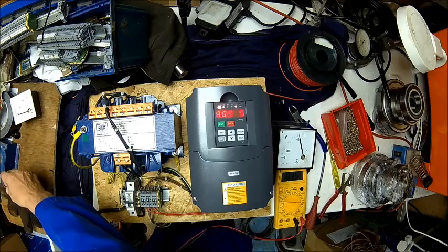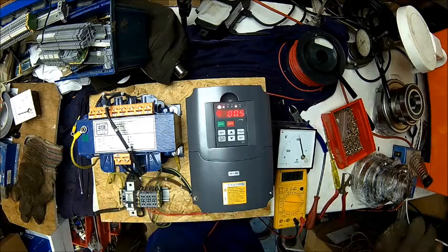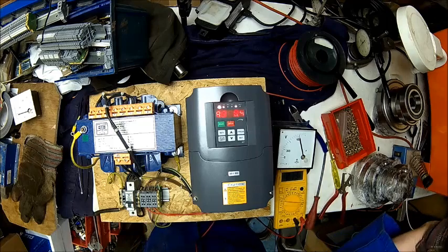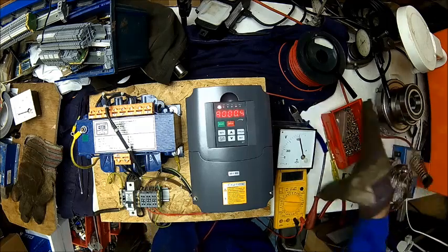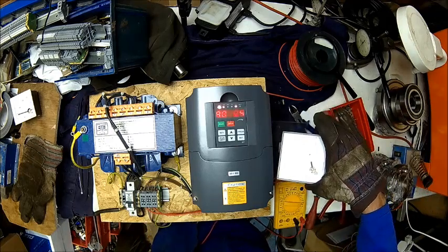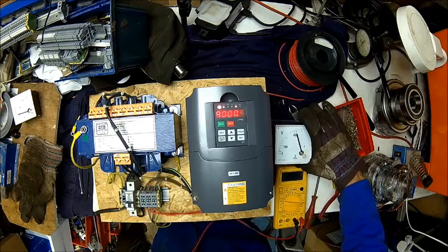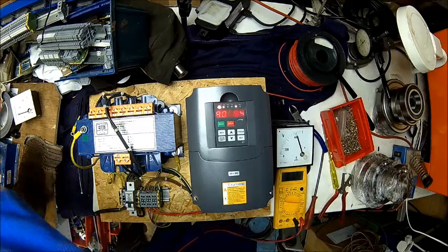But this good old thing here, which I'm only going to touch with a glove because it's a metal case and it's not grounded, so I'm going to be careful, is reading 400 volts or 410-ish volts. 415 is our target. So hopefully that proves the point that we're actually having 415 volts.